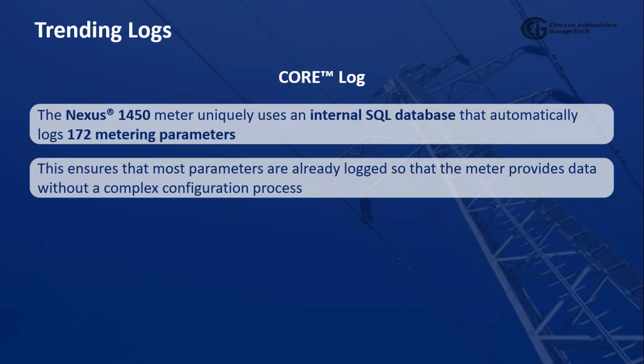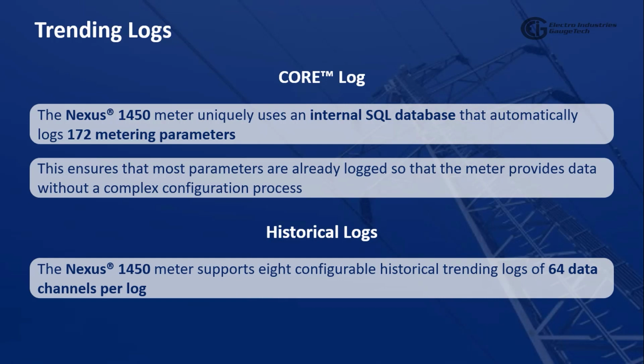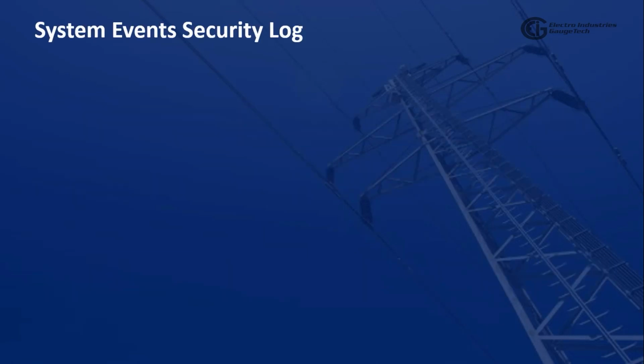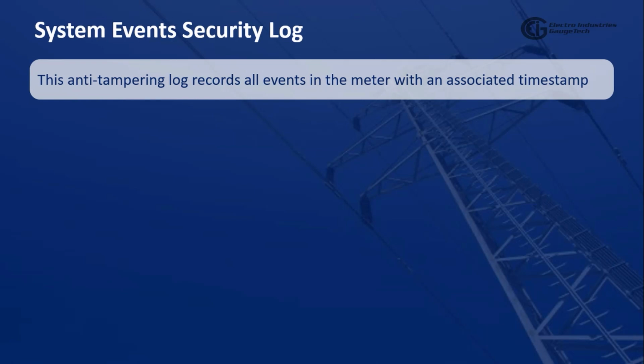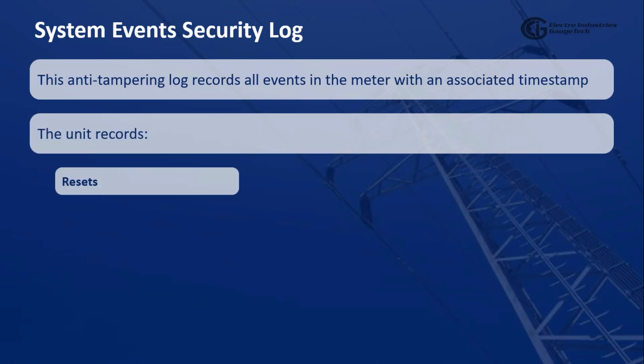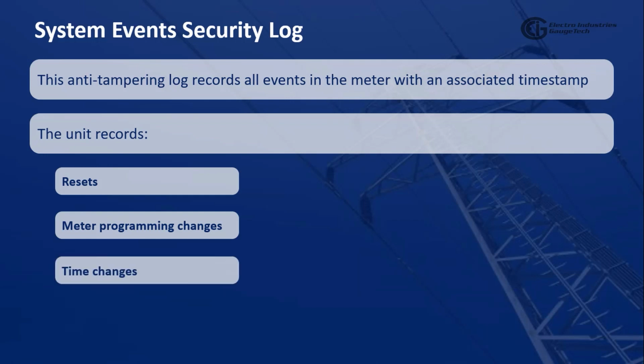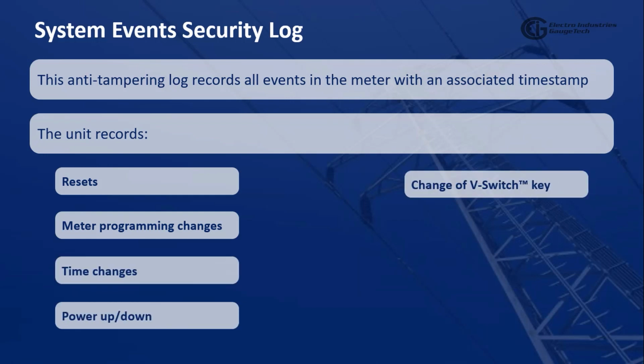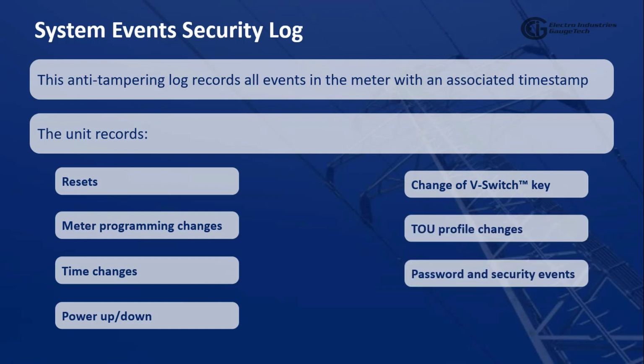Another one in trending logs is historical logs. The meter supports 8 configurable historical trending logs of 64 data channels per log. The second one is the System Event Security Log. This anti-tampering log records all events in the meter with an associated timestamp. The unit records resets, meter programming changes, time changes, power up, down, change of V-switch key, TOU profile changes, password and security events, change of firmware.